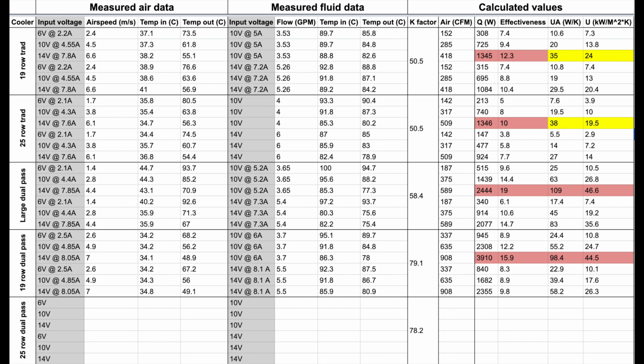So a fun piece of detail here is that if you look at the first 19-row traditional versus the 25-row traditional, you'll notice that we have a 24 for the U value versus a 20 for the U value of the 25. So that indicates that the 25 row is actually a less efficient design, but it does have larger cross surface area, so it ends up with a higher UA value. So it still comes out with a 38 as the UA, while this one comes out with a 35.